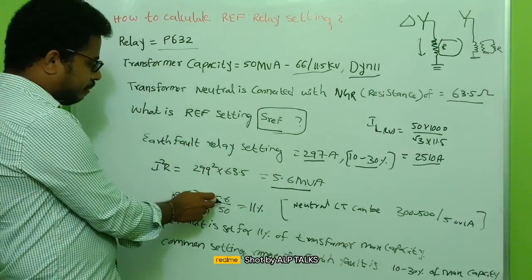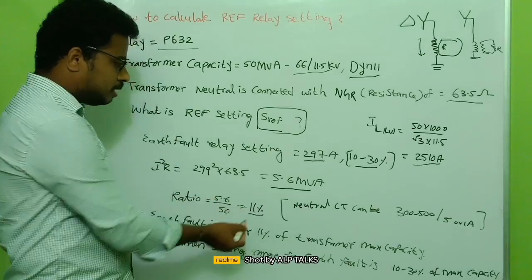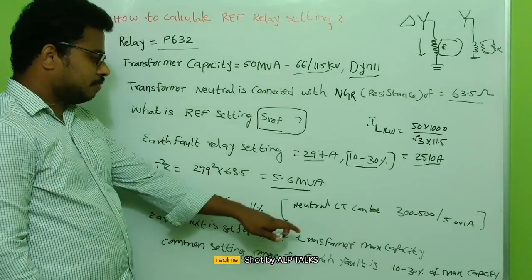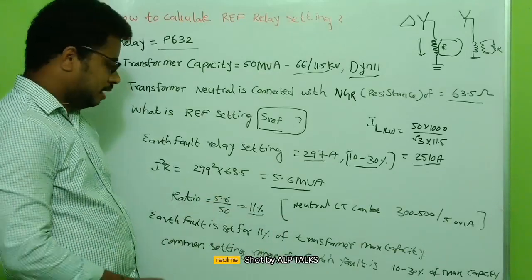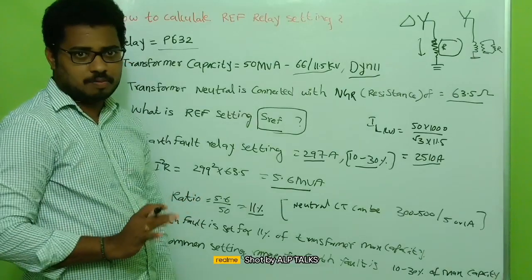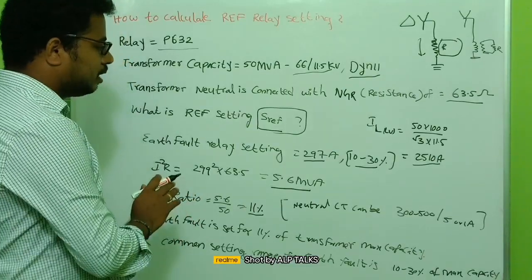So the ratio 5.6 by 50 will be 11 percent, and Earth fault is set for 11 percent of transformer maximum capacity. So common setting range for this is 10 to 30 percent of maximum capacity.